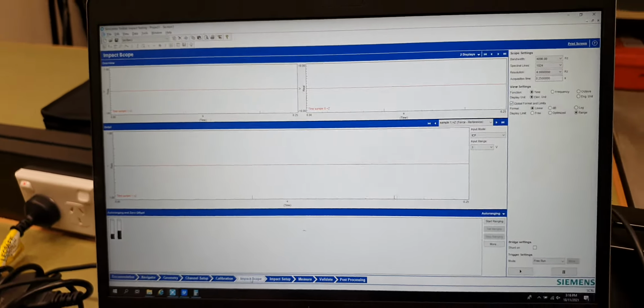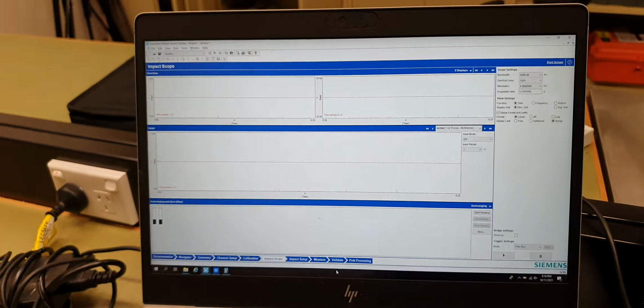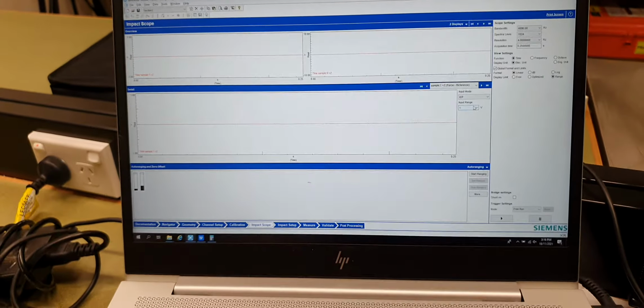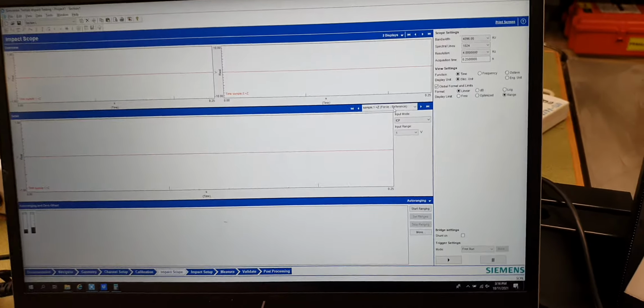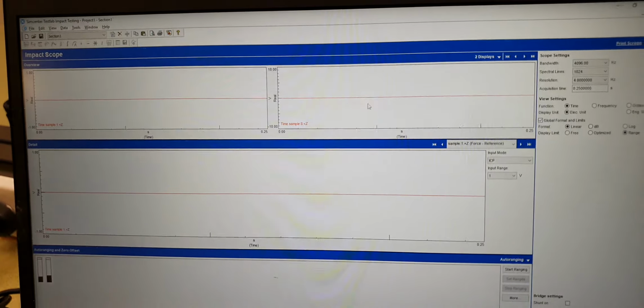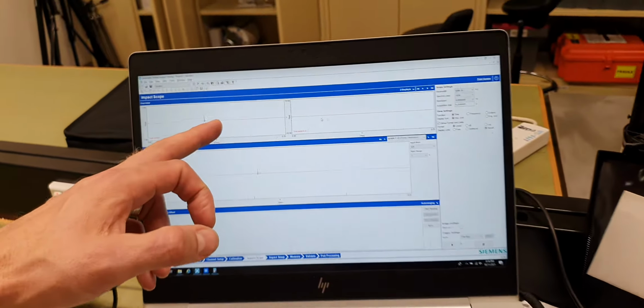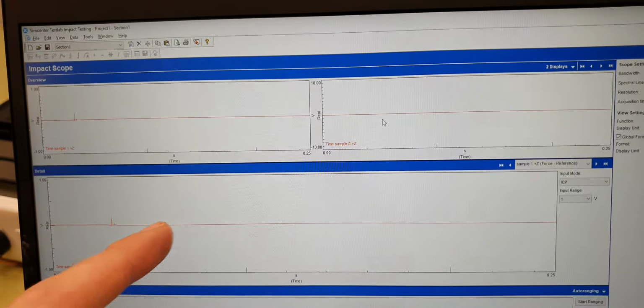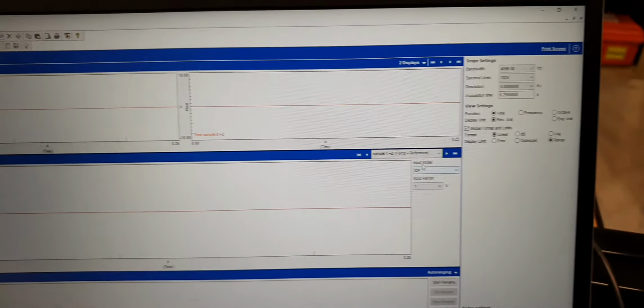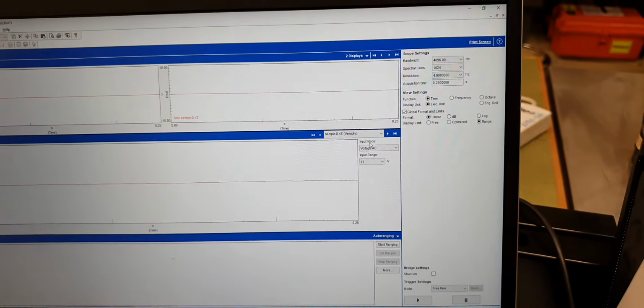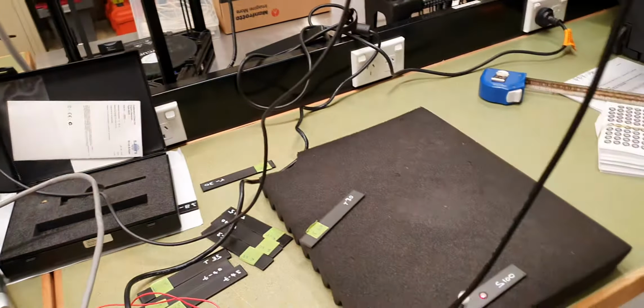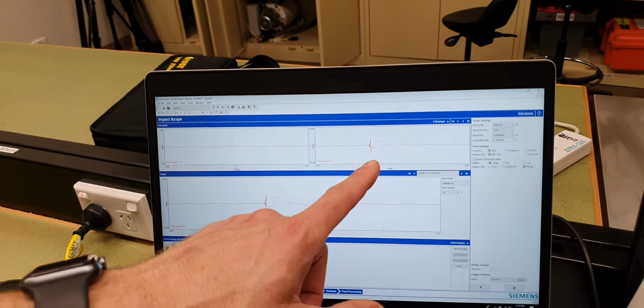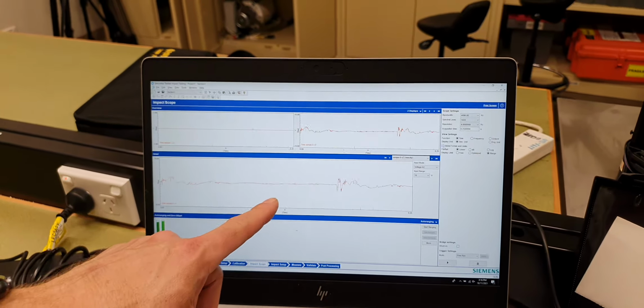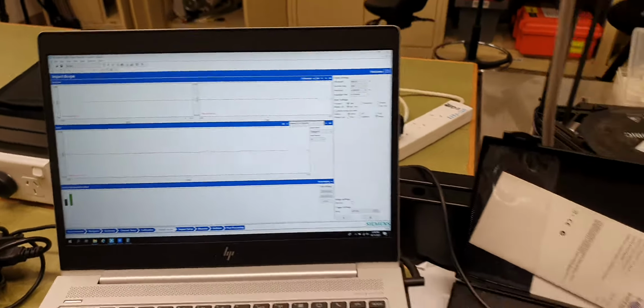So we go to impact scope, and in here I can then check the ranges on the transducers, and I can, for example, change the ranges on the transducer. So I've got two screens here which are showing me both channels. If I do some impact, you can see impacts coming through on the left. I'm also showing it again in detail in this view, and I can change the detail view to show the response measurement. And the response, I'd need to come over here and tap this one. When I tap this one, you can see the response, which is being measured by the vibrometer on the right hand side, the impact on the left, and then obviously detail view here for the response measurement.